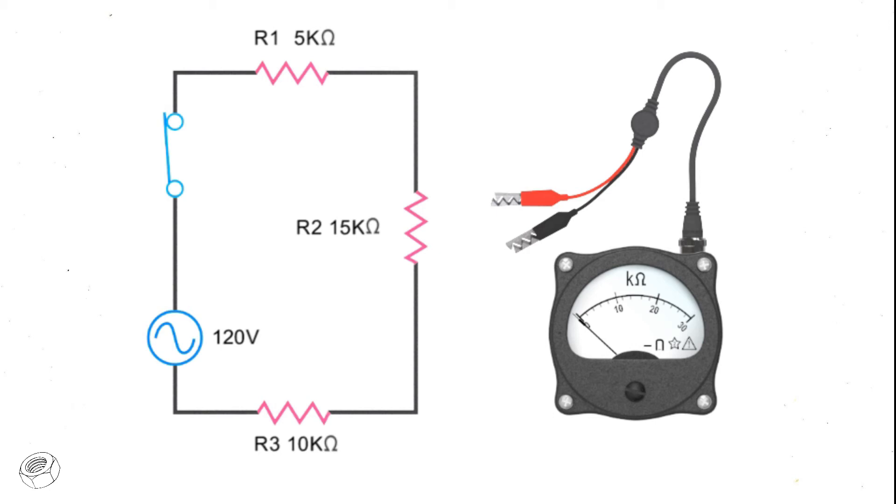Ohmmeters are never to be used in a powered circuit. It can damage the meter as well as present a safety hazard. So make sure switches are open before applying the leads of an ohmmeter to a circuit.